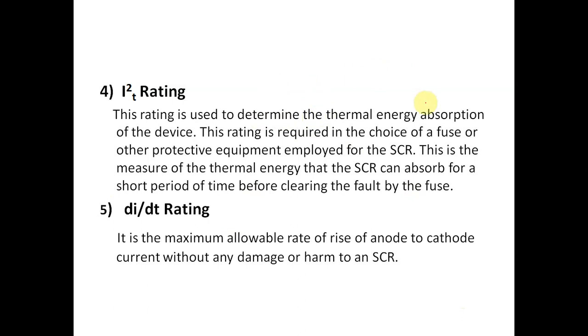This is the rating required in choice of a fuse or other protective equipment employed for the SCR. This is the amount of thermal energy that the SCR can absorb for a short period of time before the fault is cleared by the fuse. I2T rating is used to determine the thermal energy. If SCR is turned on for some time, it will dissipate heat and due to this dissipated heat, the device will be damaged. To avoid this, I2T rating is used.